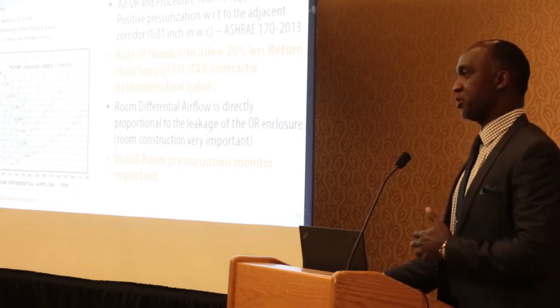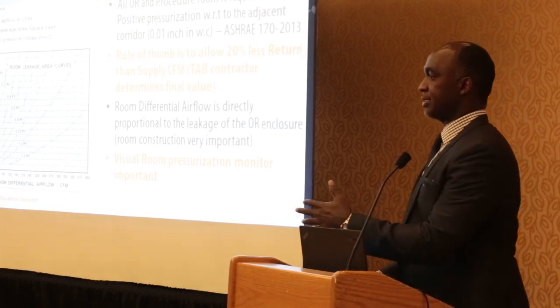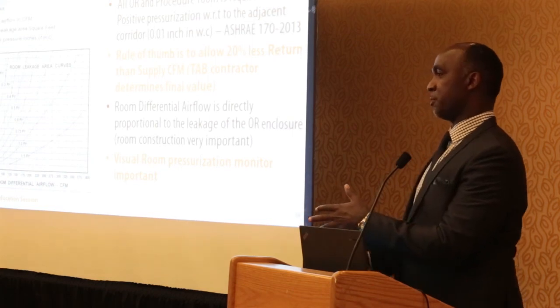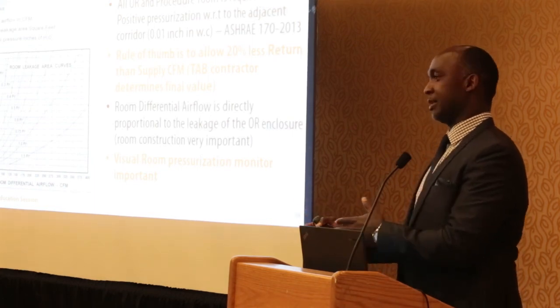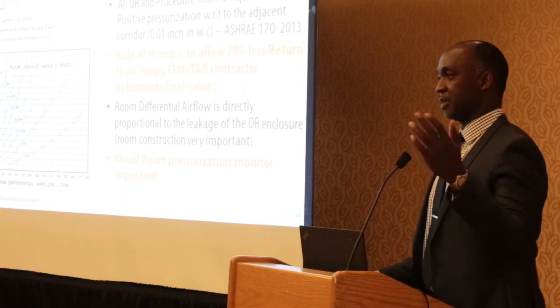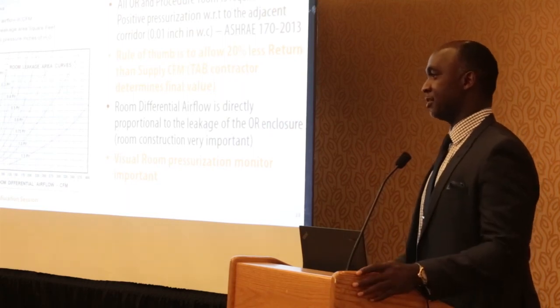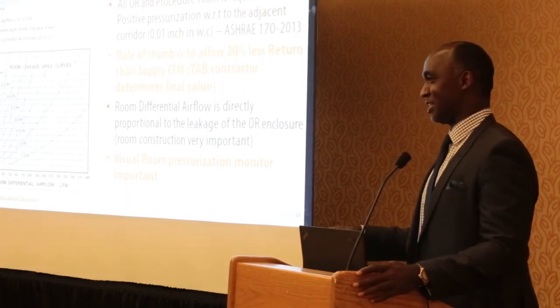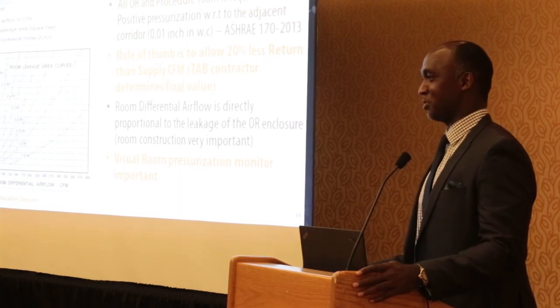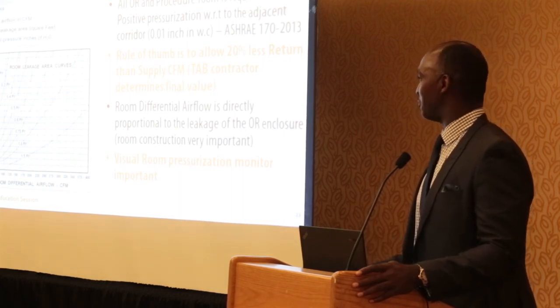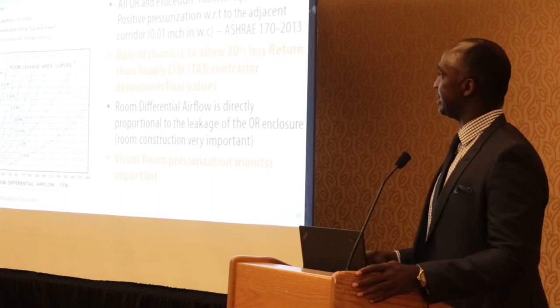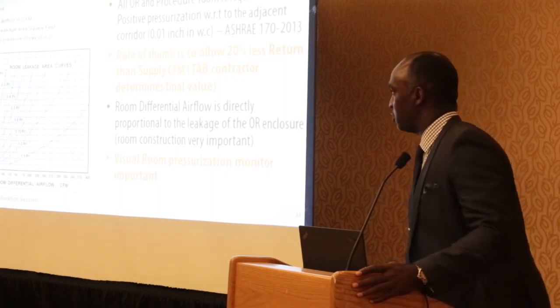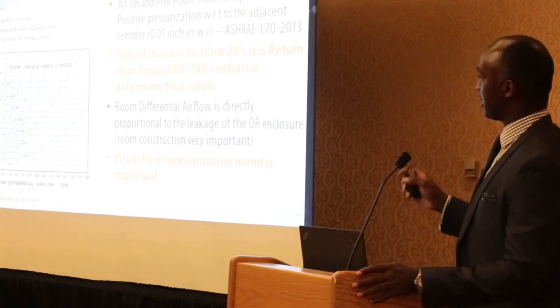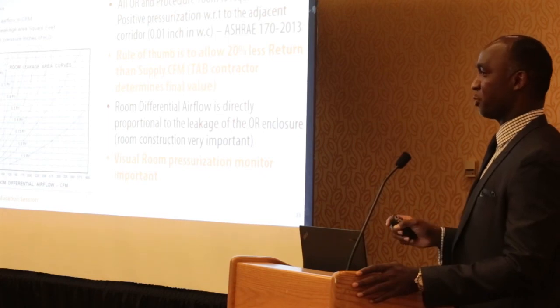But the rule of thumb for engineers is that if you're seeing a design and you're not seeing about a 20% difference between your return and the supply, you have to think about it, because you have to have less air that you're taking out of your space in your return, just to make sure that you're supplying a quality space. So that's the graph that they use to actually look at the room leakage, and that's extremely important, one of the most important parts.